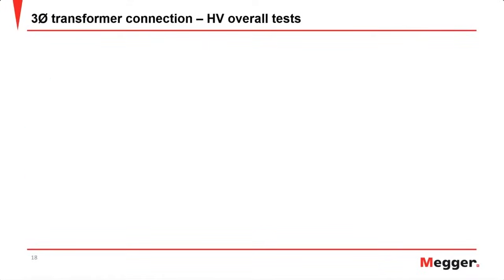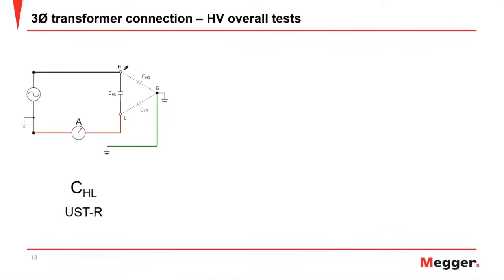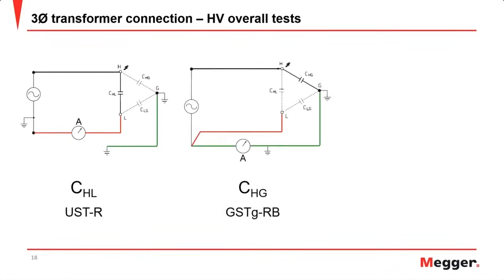Before we hop into the bushings, I do want to just show how these different measurement methods work together when we're talking about the overall transformer test, because if you're testing bushings, then for sure you are going to be testing that transformer as well. So the first test, we see here that we have our high voltage applied to the high side winding, and then we have our red measurement lead connected to the low side of the winding. And in the UST-R mode, we are only going to measure the leakage current that comes back on the red lead. With the GST guard RB, if you remember from the previous slide, when we guard R and B, we're only measuring the current that comes back on the ground channel, and that's shown here by the ammeter being solely on that ground channel.